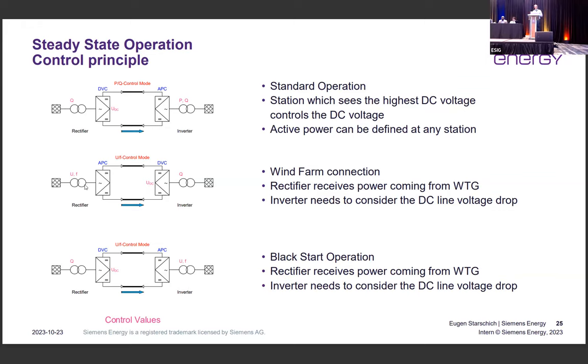On the wind farm connection, on the rectifier side, the HVDC system is controlling the voltage and the frequency, and the power flow is then defined by the wind turbine generators. Or in black start operation, as shown below, the converter station doing the black start is operating in voltage and frequency mode, and the load itself is then defined by the power being connected to the converter.